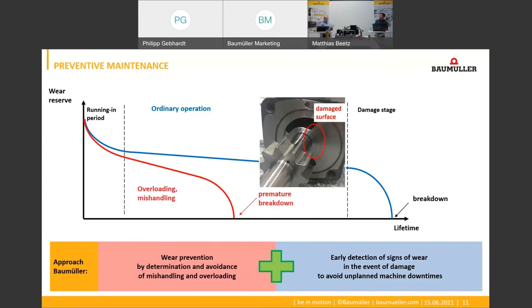And what signs of wear can Baumüller drives detect in a servo hydraulic application? There are of course different types of wear in servo hydraulics. At the hydraulic pump, for example, we can detect all wear conditions which are associated with a change in the pump leakage. And on the pressure sensor, we can detect the aging of the sensor by the increasing sensor drift.